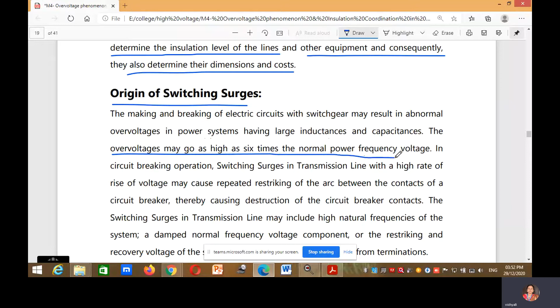Having a large inductance and capacitance, the overvoltage may go as high as 6 times the normal power frequency voltage. In circuit breaking operation, switching surges in transmission line with a high rate of rise of voltage may cause repeated restriking of the arc between the contacts of a circuit breaker. Thereby, it causes a destruction of the circuit breaker contacts.